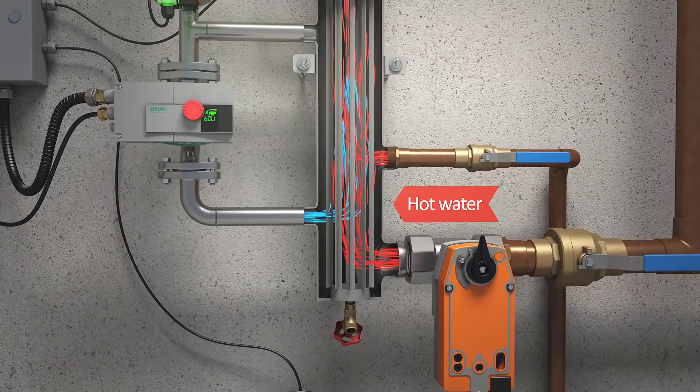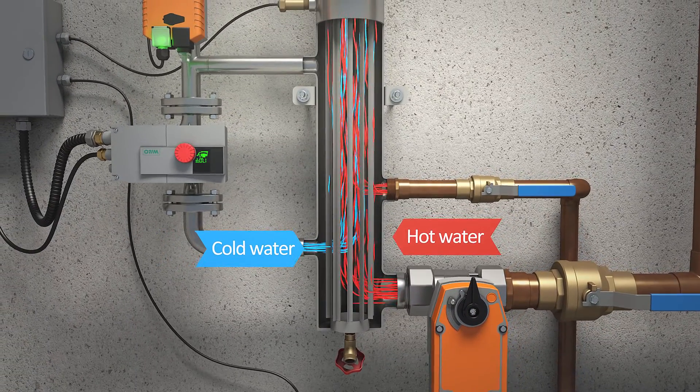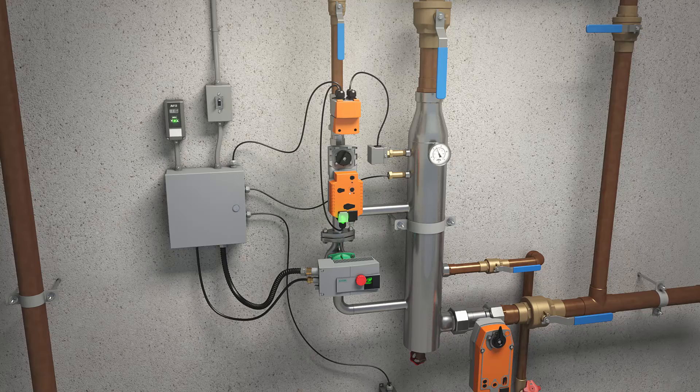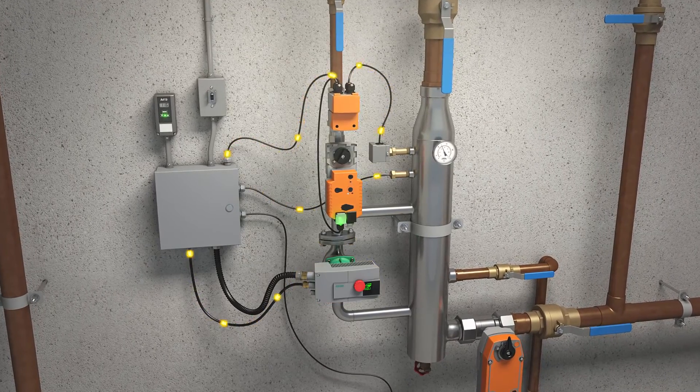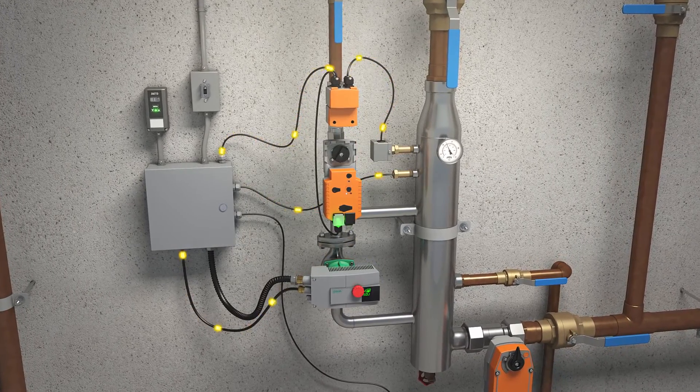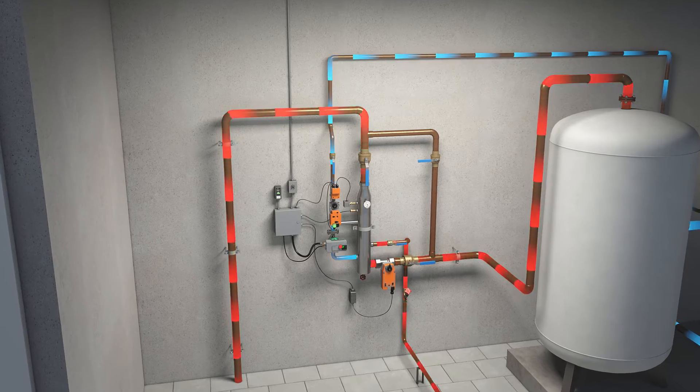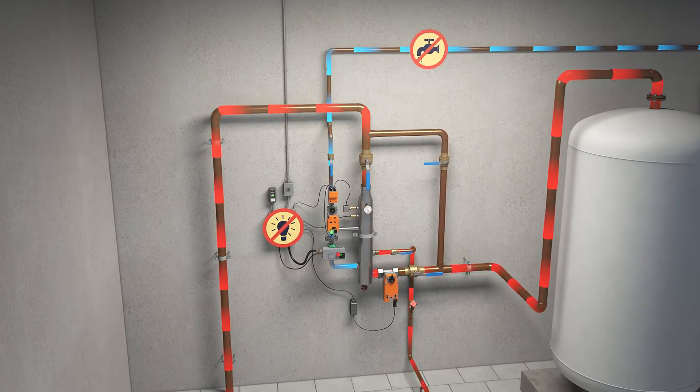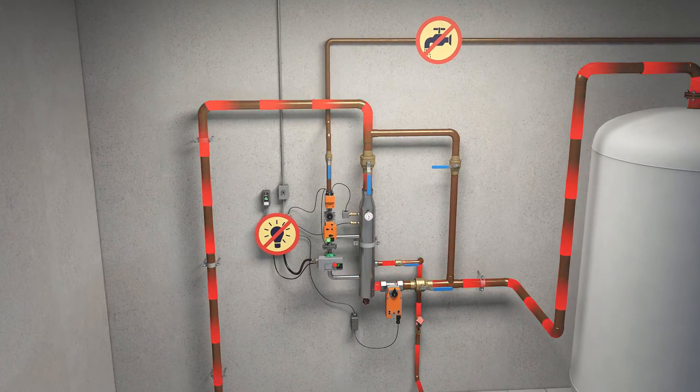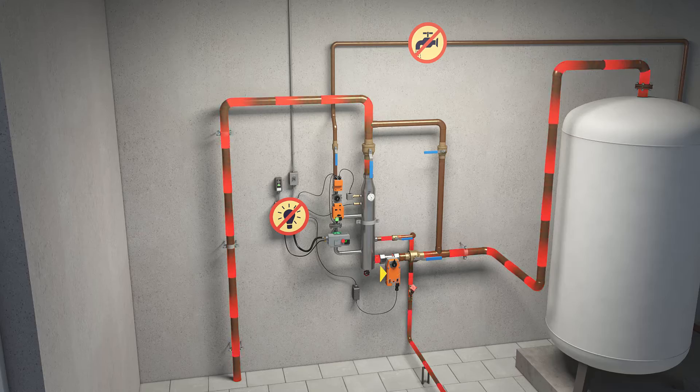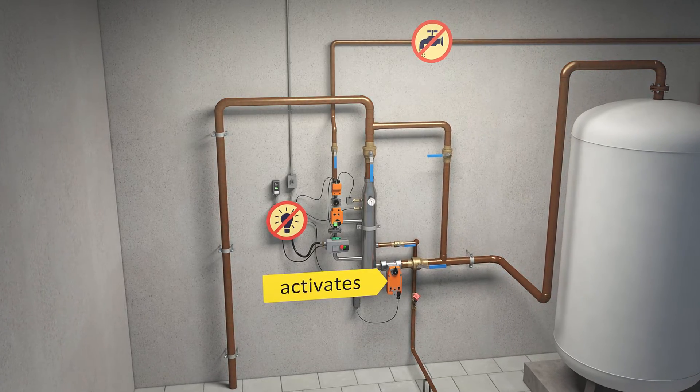Hot water enters the FlowMix mixing chamber and cold water is blended in. Sensors on the outlet of the system signal the circulation pump and injection valve to regulate the appropriate ratio of hot and cold water. In the event of a power failure or interruption to the cold water supply, an independent fail-safe shut-off valve activates to disengage hot water supply to the line.